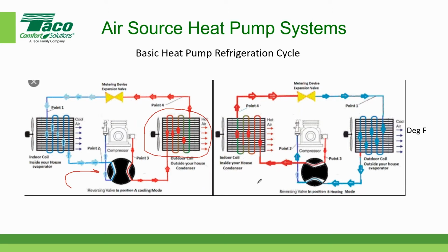So that shows you how the reversing valve can take a conventional heating cycle on this side here and convert it into a conventional cooling cycle over here. So instead of physically swapping equipment around, which of course is not practical, we have this reversing valve that changes the direction of the refrigerant, where before the refrigerant went to the condenser, which was responsible for making hot water, in this case hot air, but in the previous diagram hot water, and then absorbing heat from the outside air. And then the reversing valve redirects the refrigerant to change the functionality of the two components.